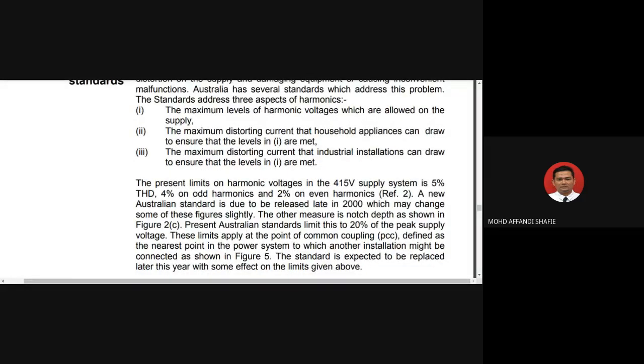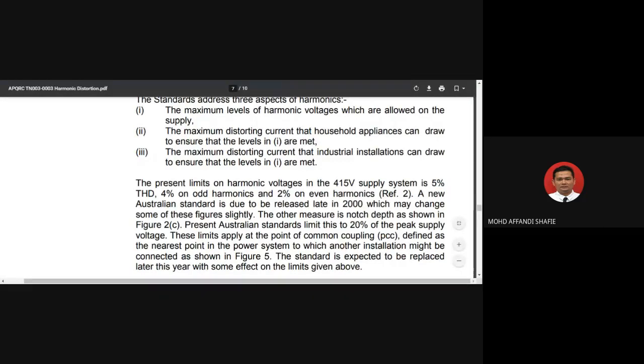So the present limits on harmonic level in 415 volt supply system is 5% THD, 4% on odd harmonic, and 2% on even harmonic. So you can refer to reference number 2 lah. So a new standard is due to be released. Okay, this one again.